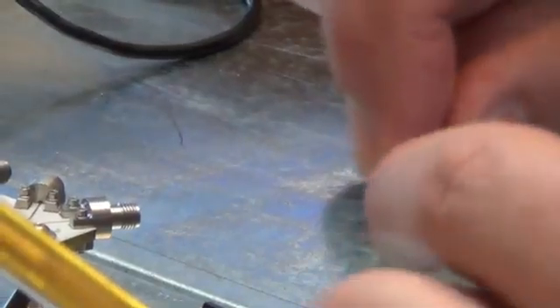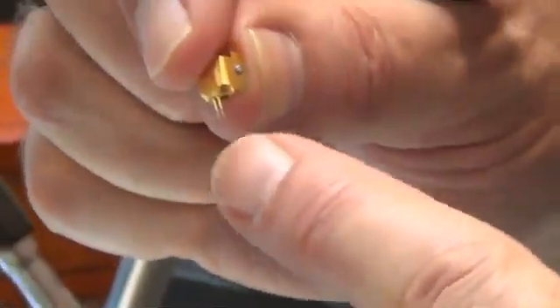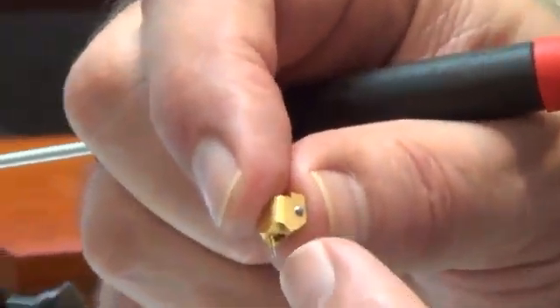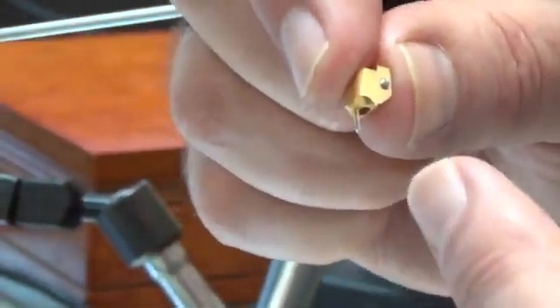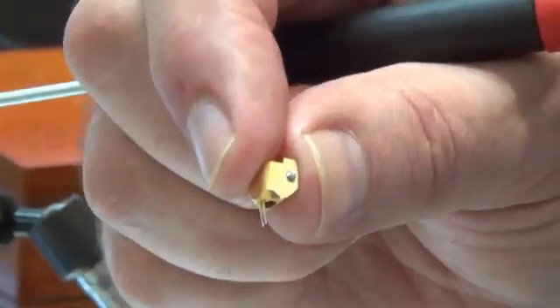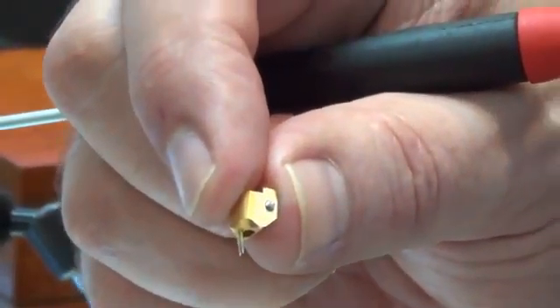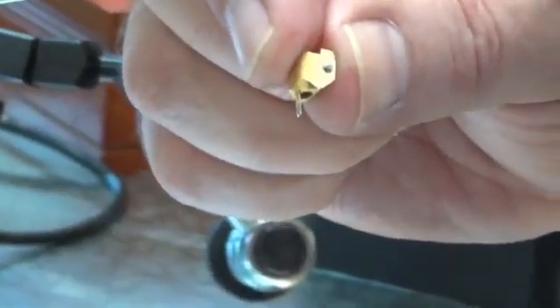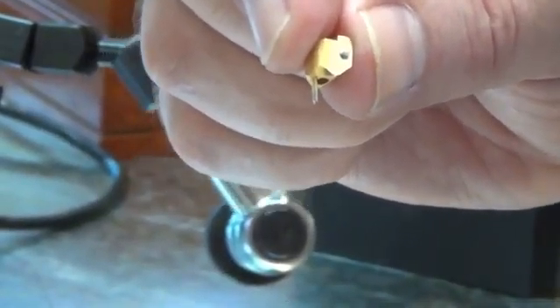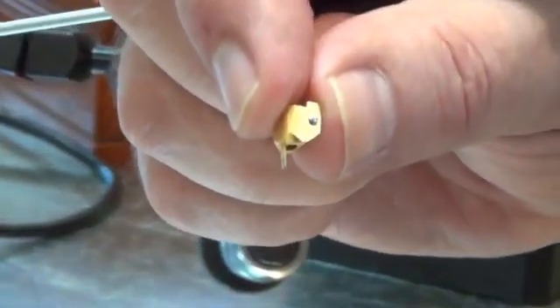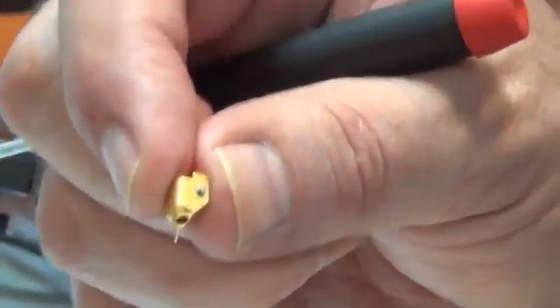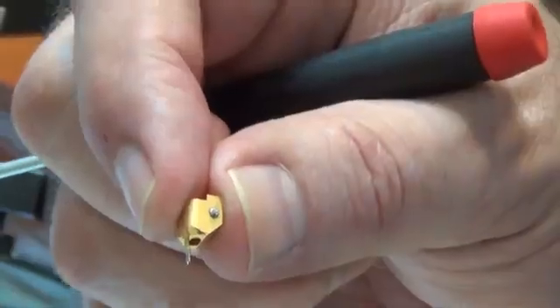This one here, if the signal pins and the ground pins are one behind the other, then what you want to do is use this one here. This has the 2 ground pins that you can put in here, and the probe tips would come out here. So that places the ground pins directly behind the signal pins. I find a lot of packages for processors or high-speed FPGAs, for some reason, put the ground pins directly behind the signal pins, and it's almost impossible with a single probe to make a measurement differentially. But with this ground collar, it places it in a proper position to gain access to your ground.